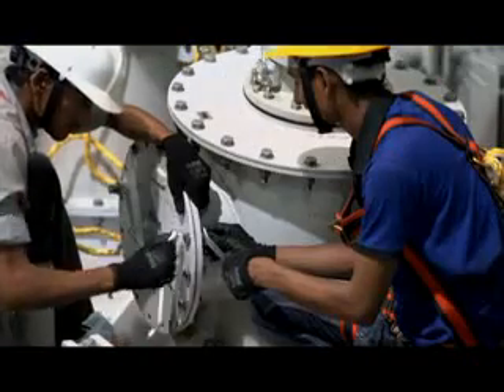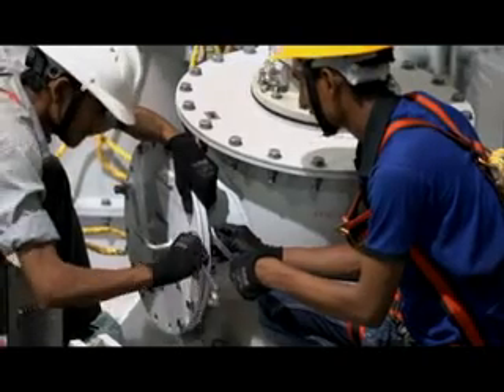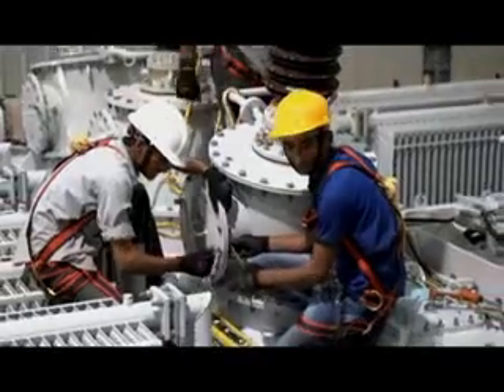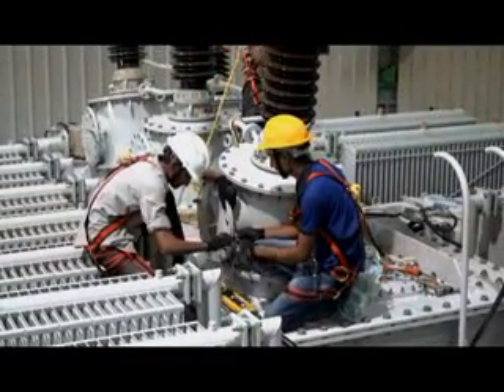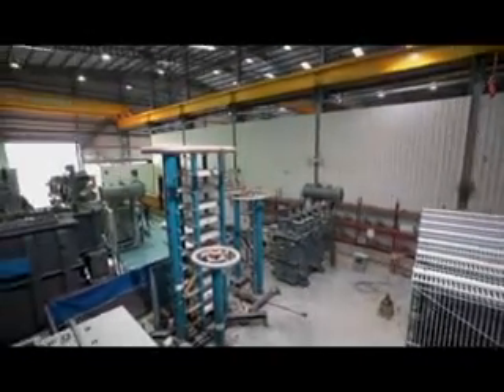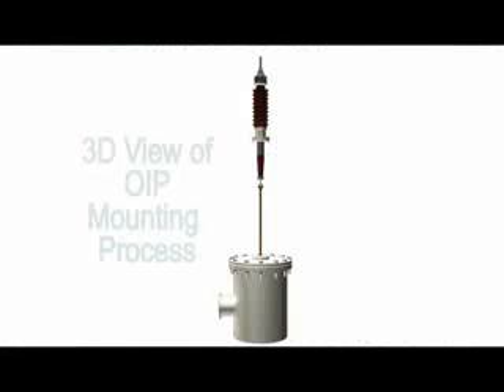Brown glazed porcelain insulators of high strength are used as air end and oil end insulators. Air end porcelain is normally provided with a nominal total creepage length of 25 mm per kV of the rated voltage. Oil end porcelain is cone shaped without shells. Air end porcelain is provided with alternating long and short shells.